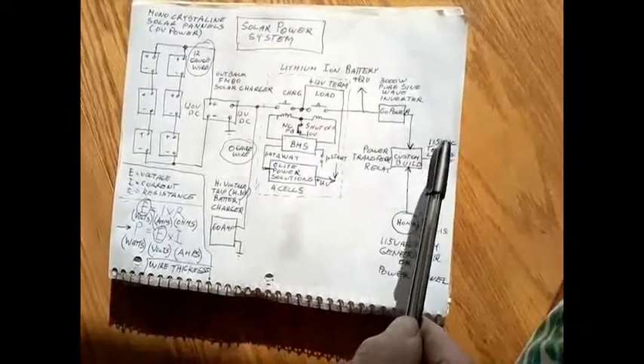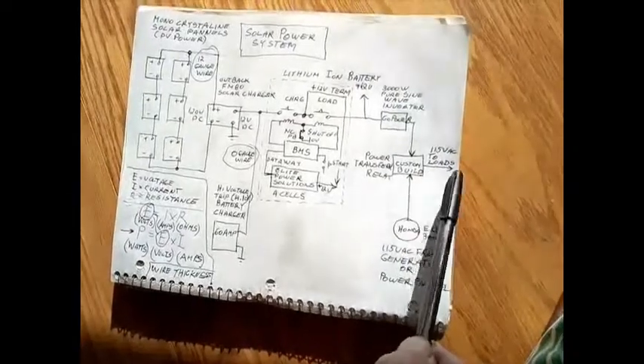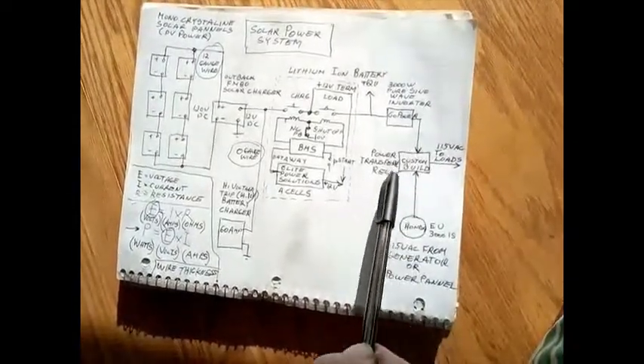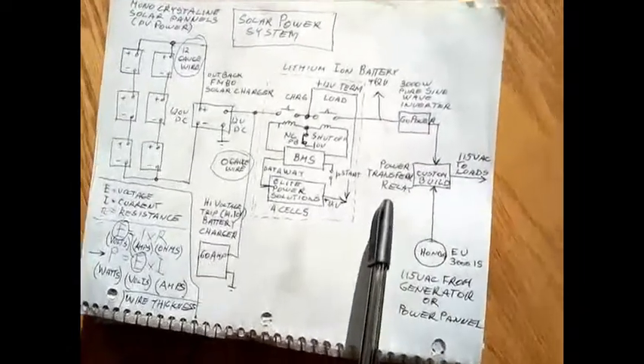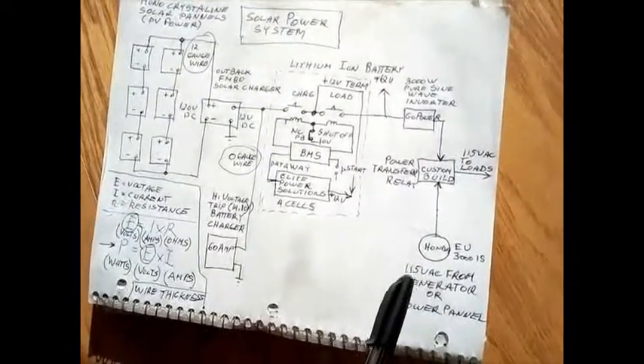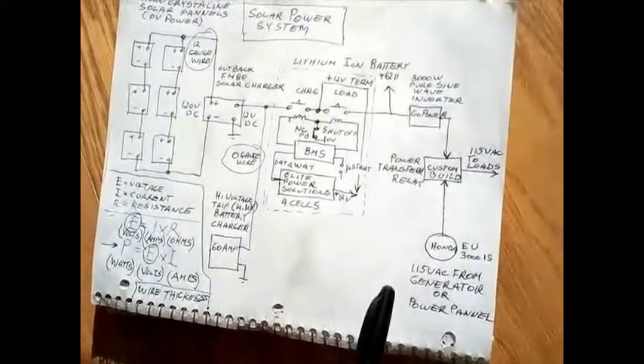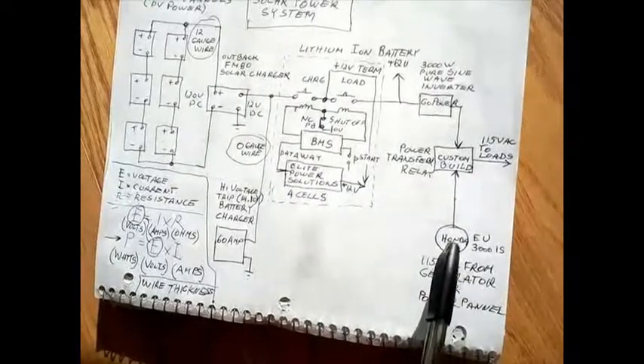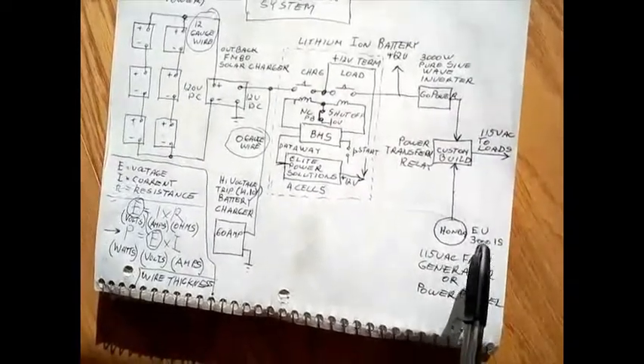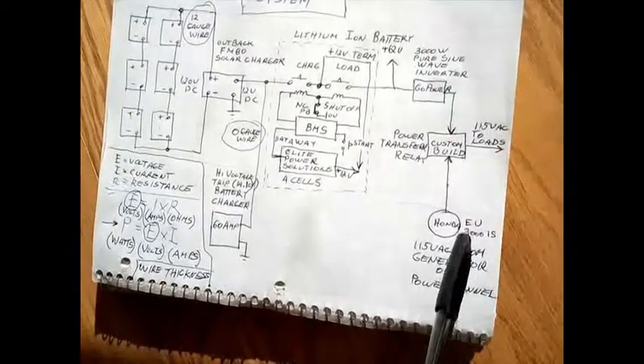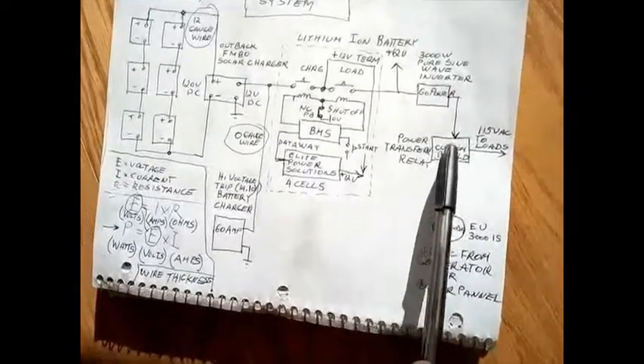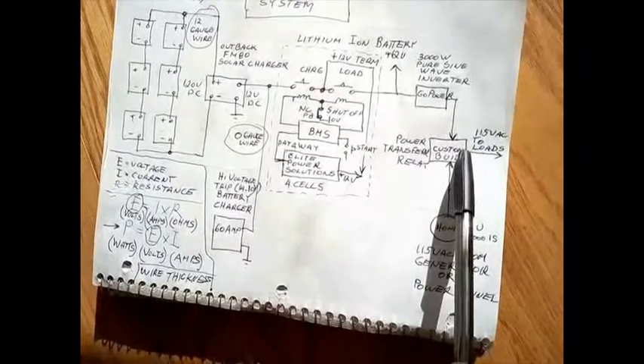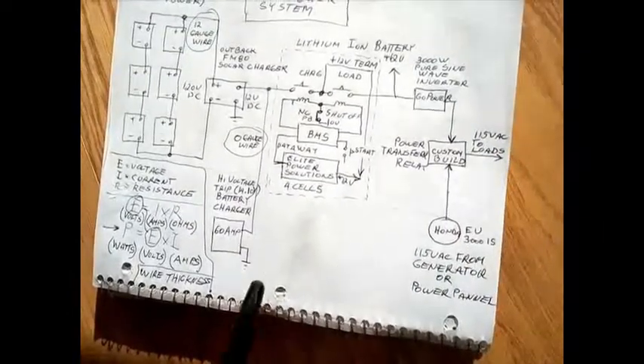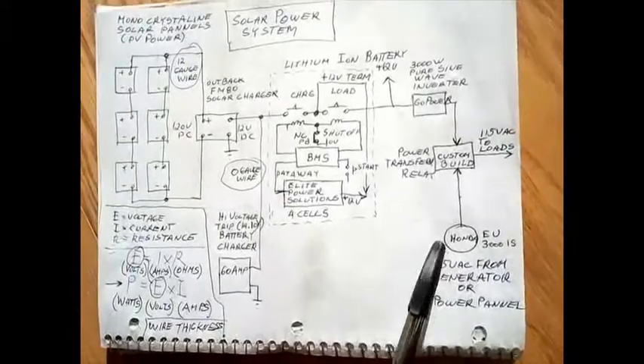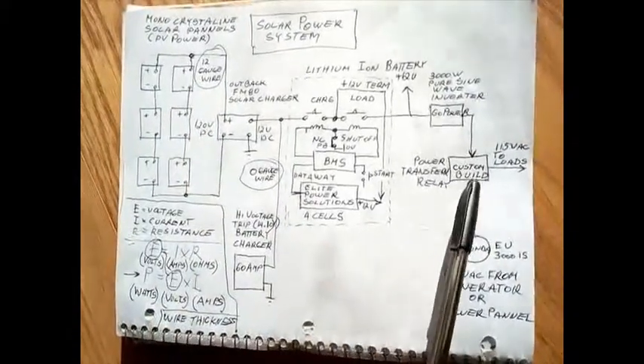In the final 115 volts output to the loads, we have our own custom built, custom designed power transfer relay. If it's a rainy day and we don't have solar energy available, we might consider using a generator, such as a Honda EU3000IS, which is electric start, and then this will switch the contacts of the power transfer relay and supply all the loads. If the generator isn't running, it's all taken over by the solar system.